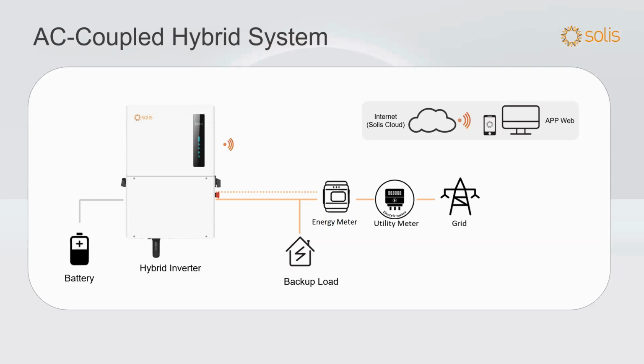And you can set this up just like this. Now, this is charging off the grid in this case. This is something you can't do in California — they won't allow you to charge the battery off fossil fuel power and then discharge it, potentially onto the grid. But here, we're using the battery to run the backup loads, so we'll set the inverter to charge off the grid. That's one of the things you'd do going into backup mode — you'll set the inverter to charge off the grid, because normally it's set not to charge the battery off the grid, only off of PV.